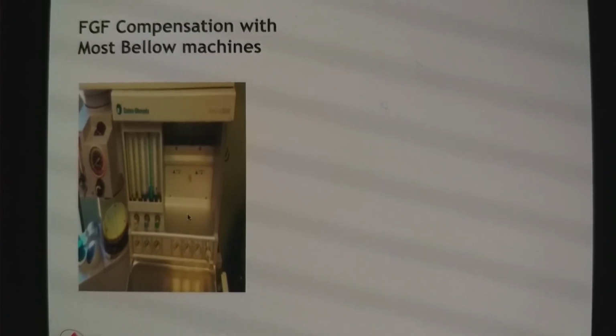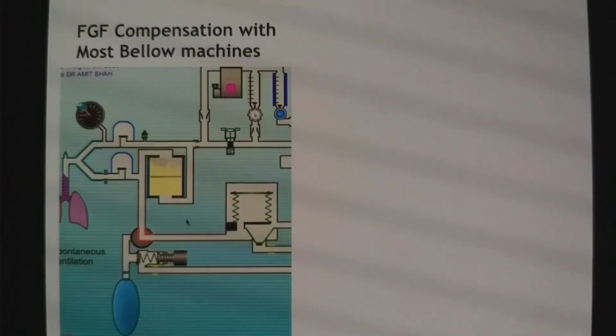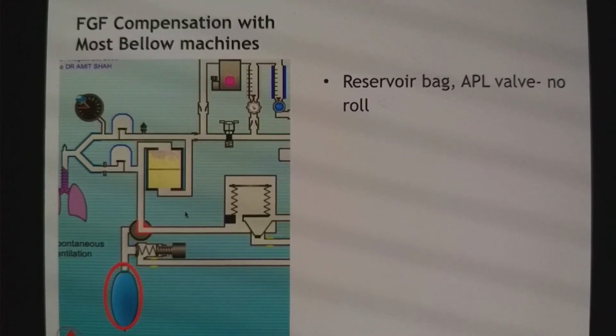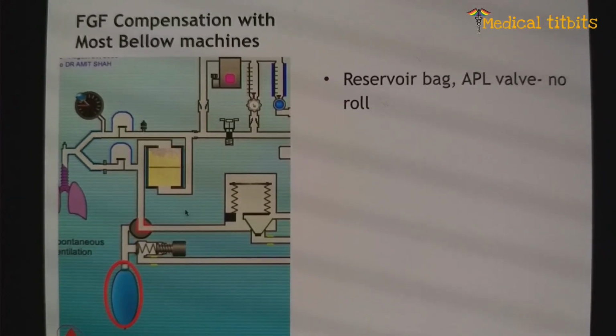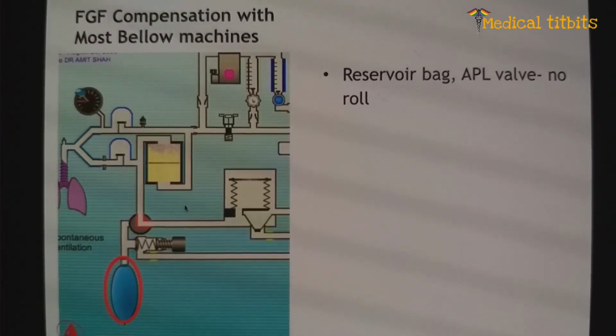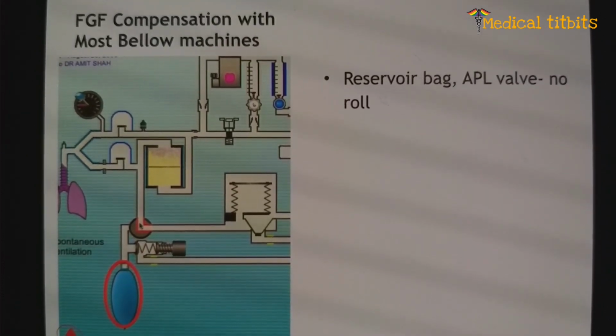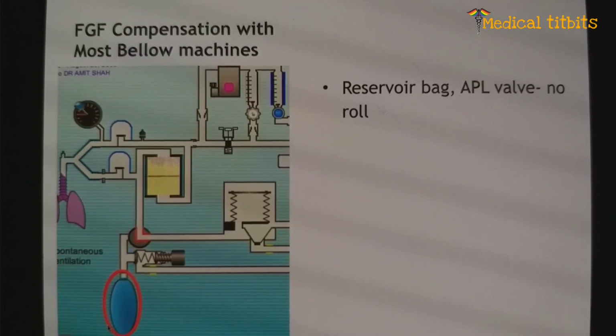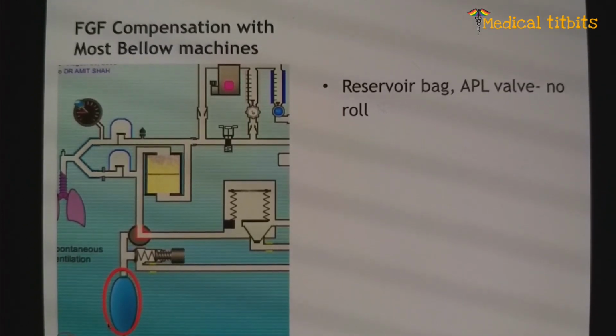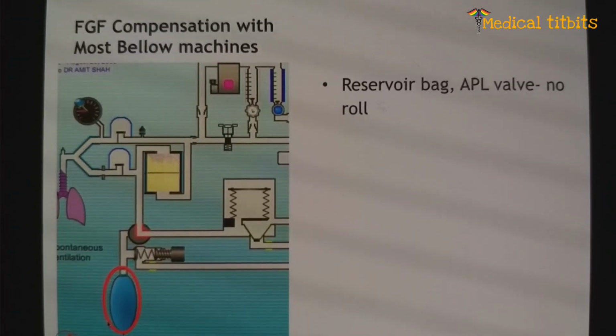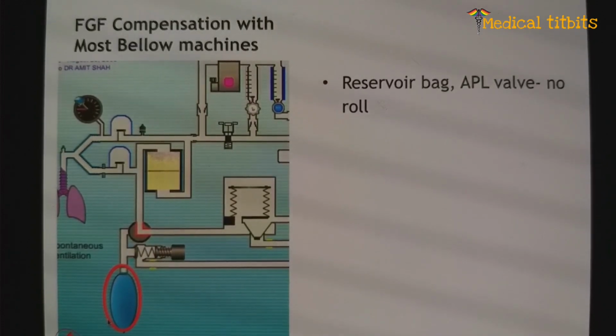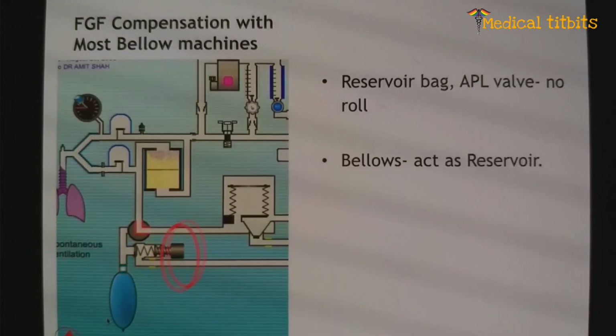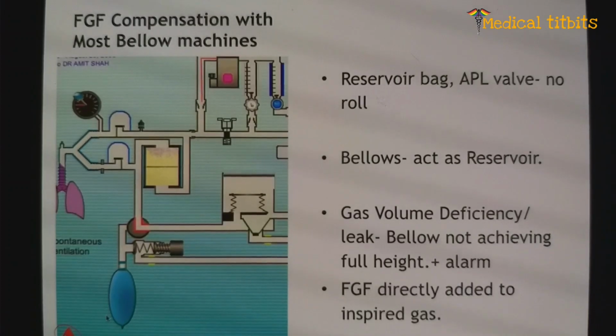Now fresh gas compensation, which is there with most of the bellows machines. Here, when you switch over to the ventilator, you must have seen the reservoir bag and APL valve, because they are cut off from the system, have no role. You squeeze that bag, nothing will happen. It will just take out the gases from your APL valve. Nothing else will happen. So what is the reservoir for the system? So bellows are the reservoir for the system.